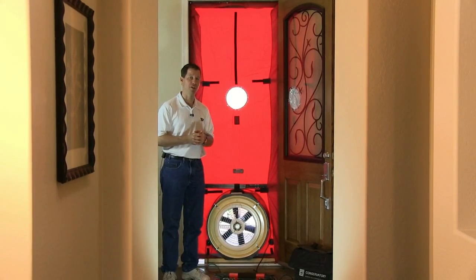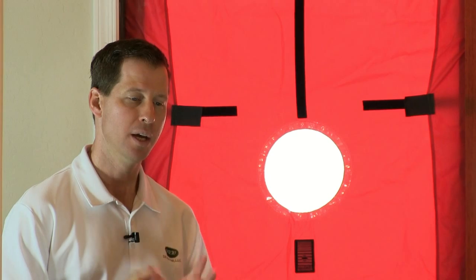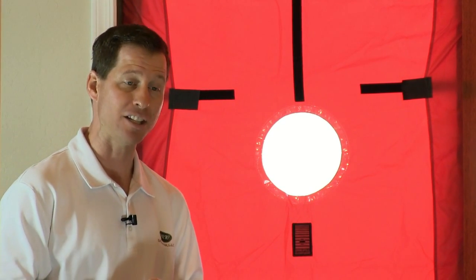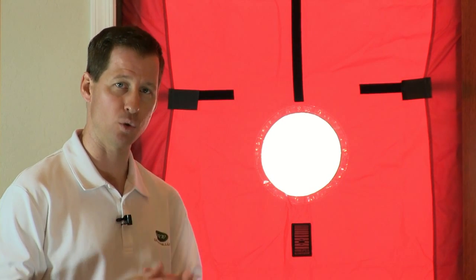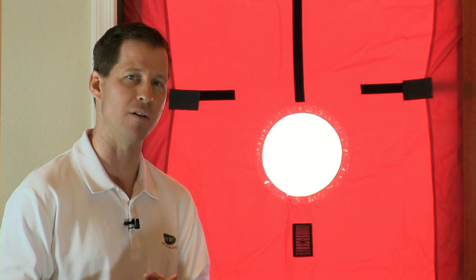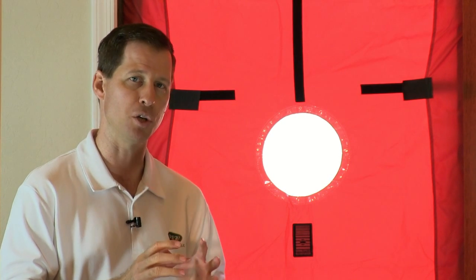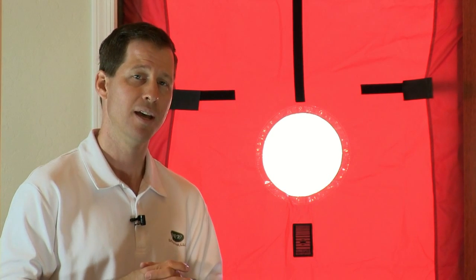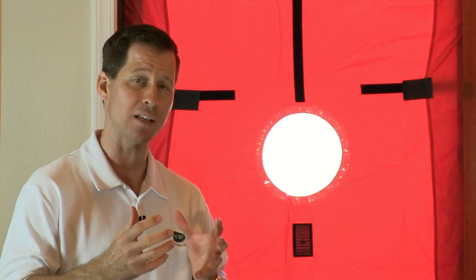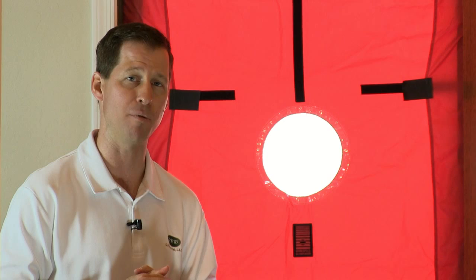You can see that the door looks a little bit different here. The blower door is set up and we're going to run this test. The idea is that any air that you take out of the house using a big fan like this has to be replaced with air coming in through holes. The blower door, with the digital gauge, allows us to calculate how much airflow is going through the envelope. Holes would be recessed can lights, holes in a door or window. Builders doing ENERGY STAR like Shea Homes work really hard on putting in good windows, excellent sealed doors, and airtight insulation contact recessed light fixtures.